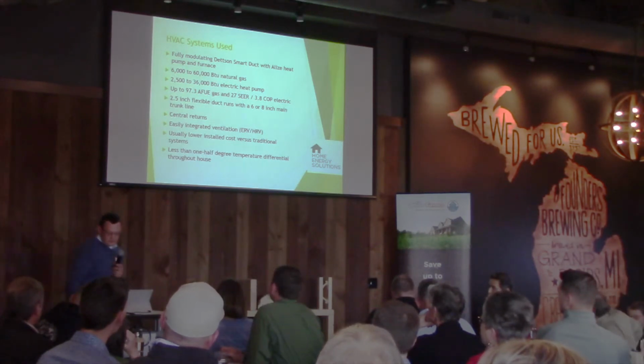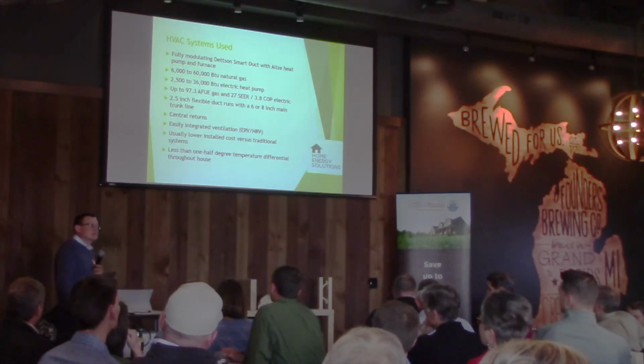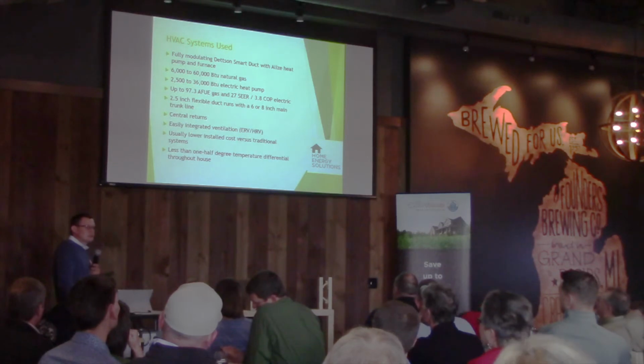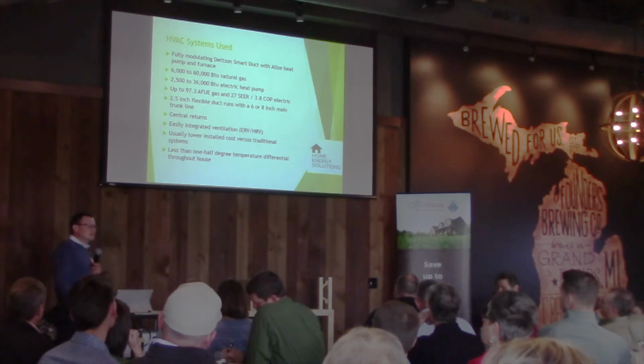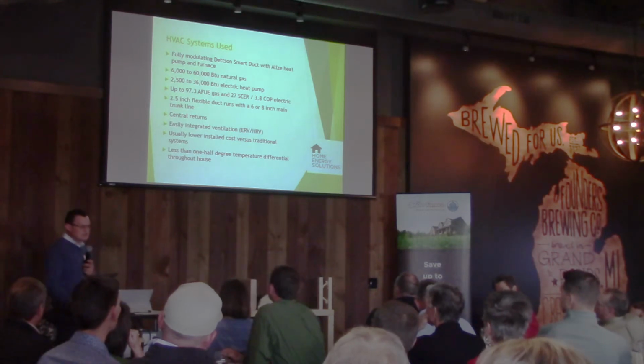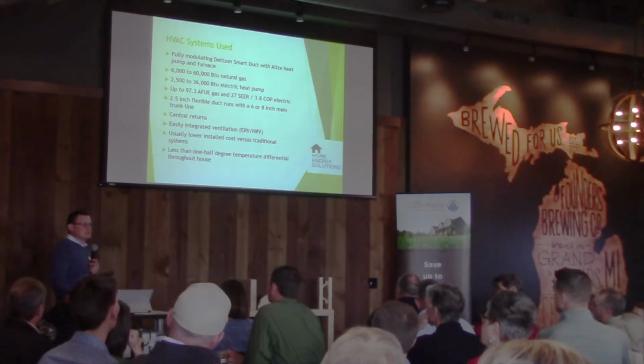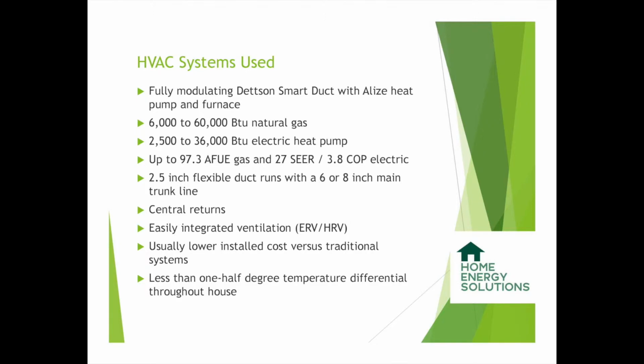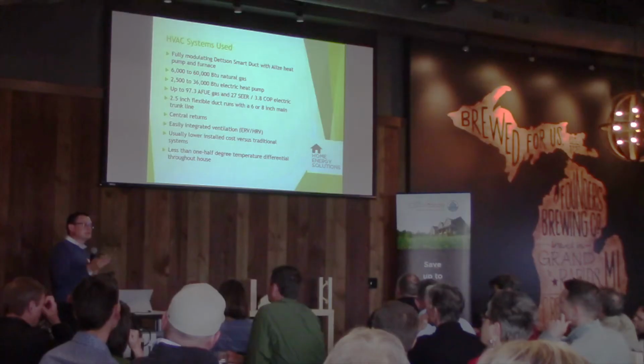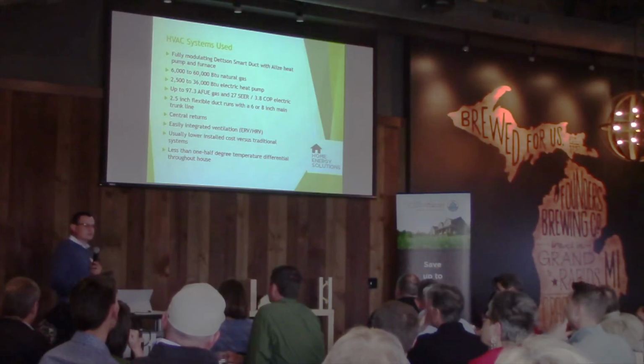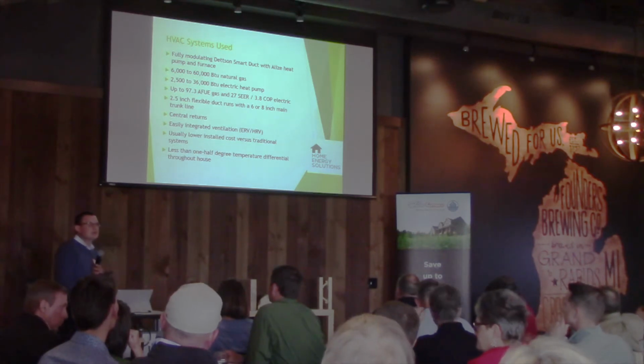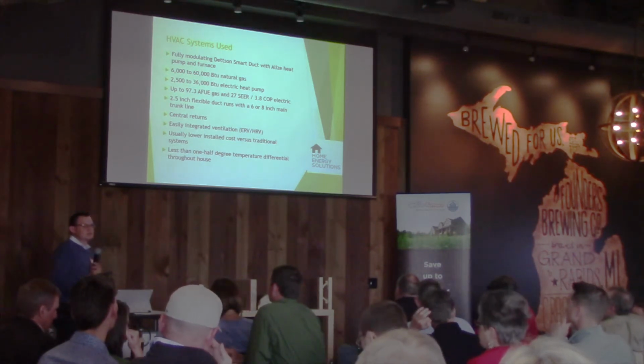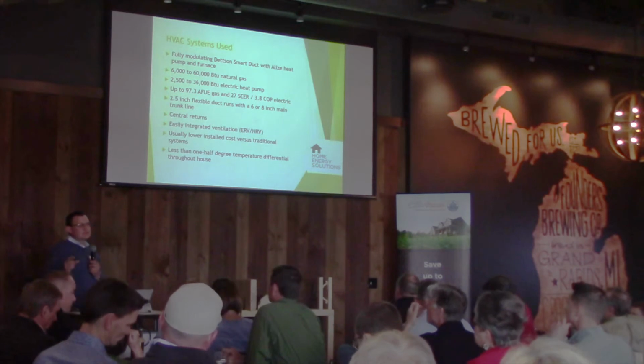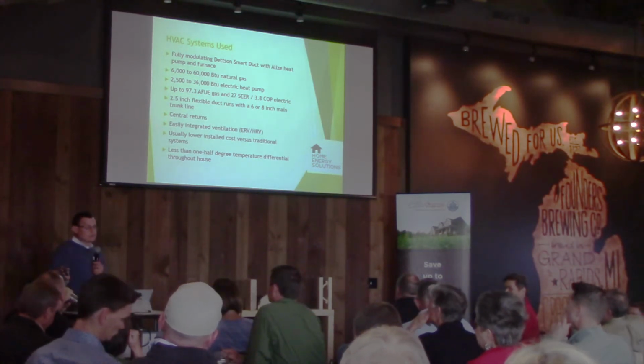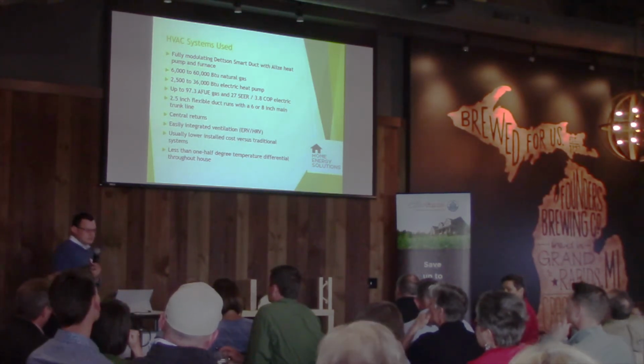The other really nice thing about this is that in the first 3 or 4 houses I went around with a temperature sensor and we did some pressure diagnostics. When it's installed, we're getting less than a half a degree of temperature variation throughout the entire house, whether the doors are open or closed or wherever you are in the house. And our pressure differentials are almost zero as well, so that 1/4 inch to 3/8 of an inch undercut in your doors actually is effective, and you're not overpressurizing bedrooms and such.